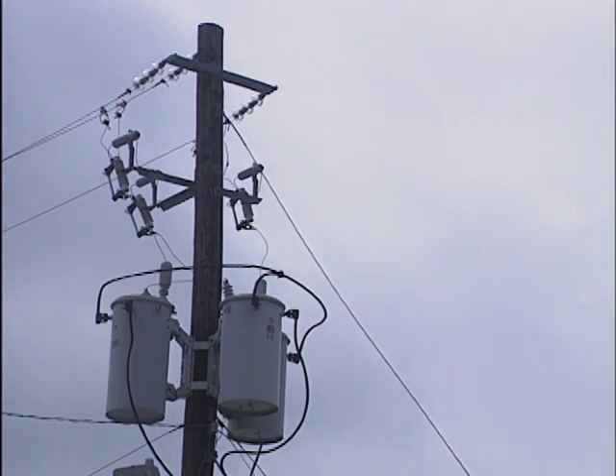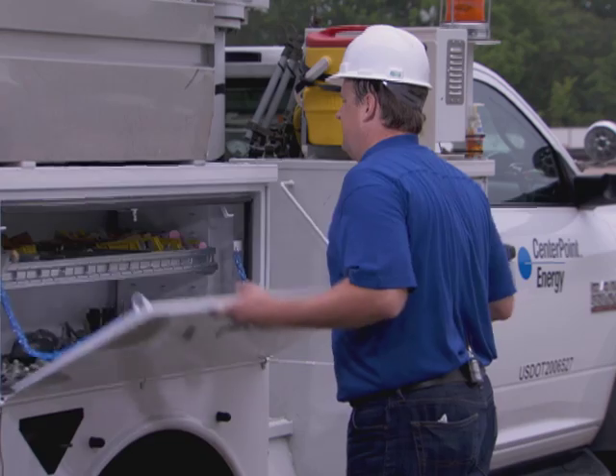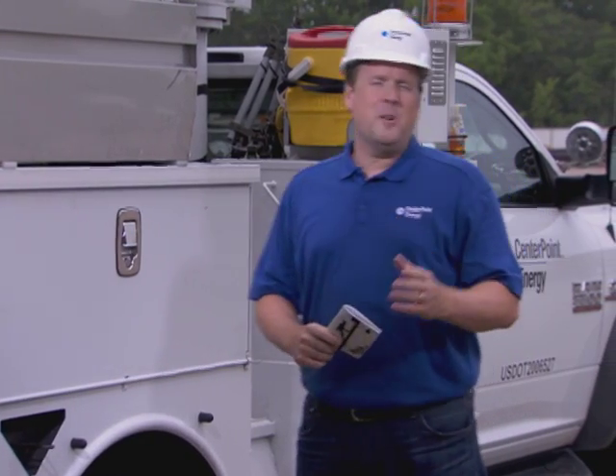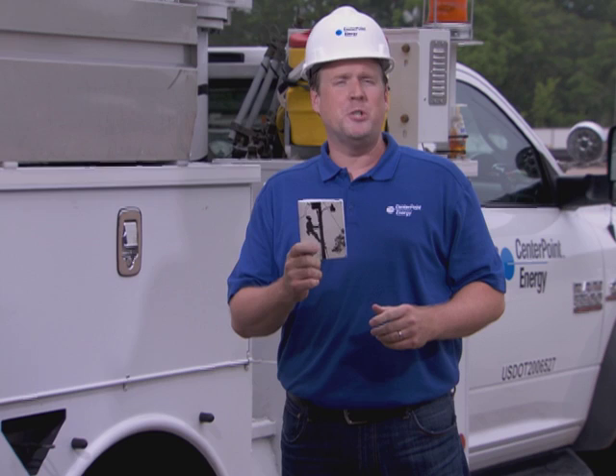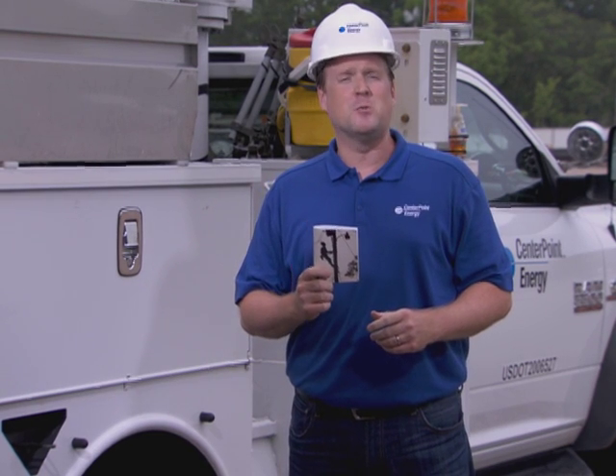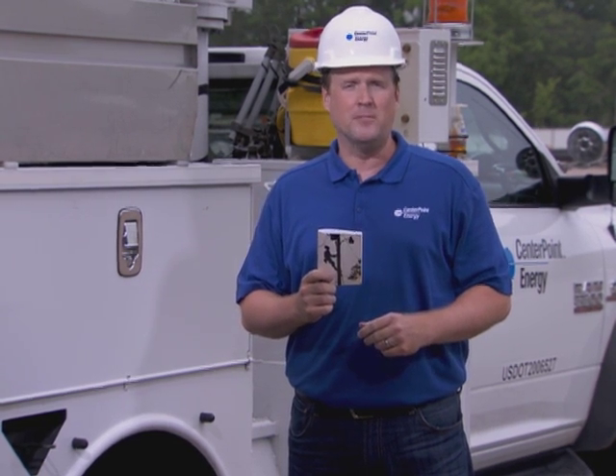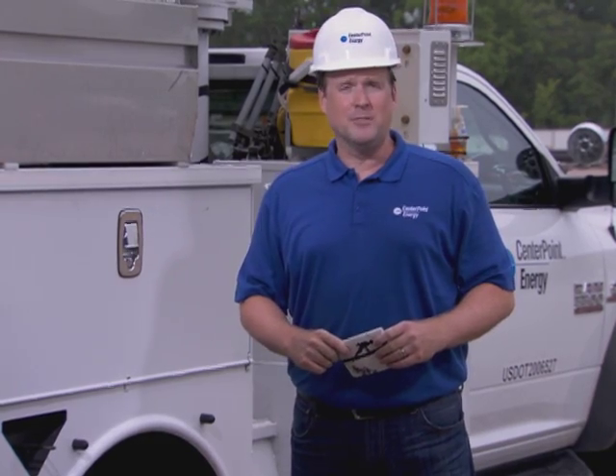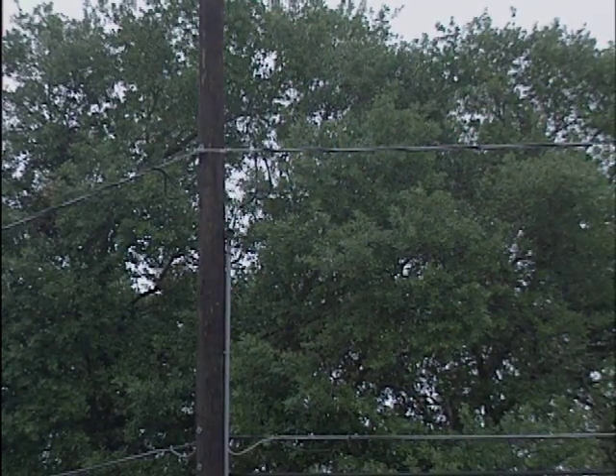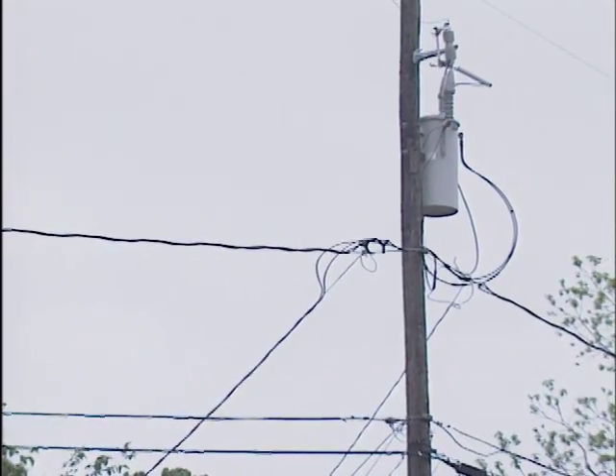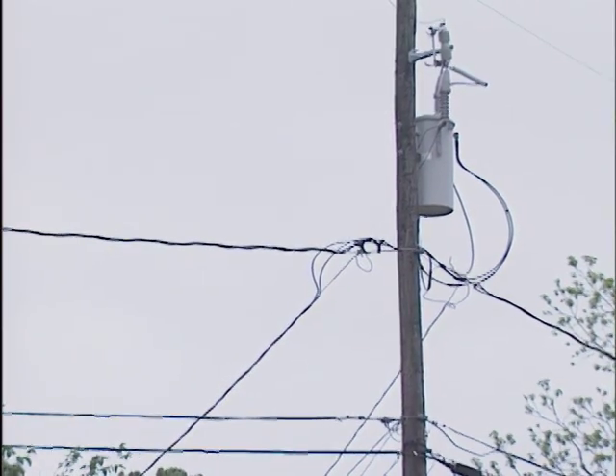CenterPoint Energy uses both delta and Y transformer connections to provide a wide range of secondary voltages. A listing of the various voltages and transformer connections can be found in your Service Restoration Handbook. If you have any questions while out in the field, just ask your foreign crew coordinator. A couple more items worth pointing out. There are no parallel secondaries in our overhead system. Single-phase secondaries are individually connected, not tied to several transformer stations. Therefore, service will not be maintained if the individual transformer fails.